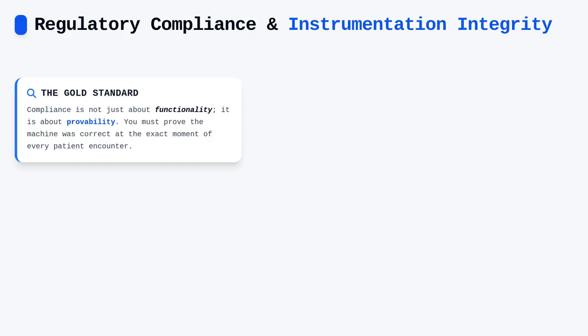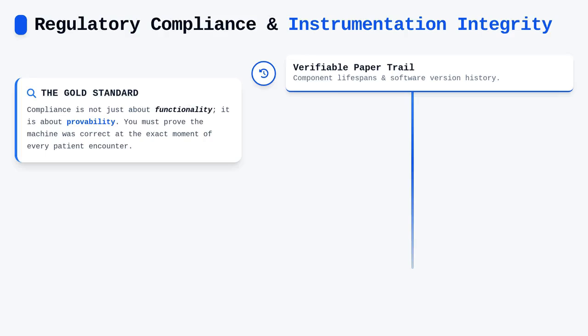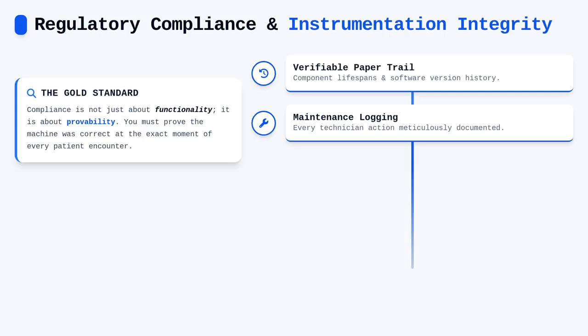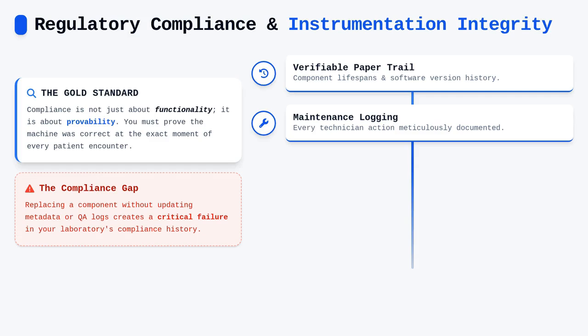Compliance is not just about keeping the machine running. It is about proving that it was running correctly at the time of each patient encounter. Regulatory bodies require a verifiable paper trail that tracks component lifespans, software version history, and all maintenance actions performed by technicians. If you replace a sensor but fail to update the system metadata or log the change in your quality assurance records, you have effectively created a gap in your laboratory's compliance history.